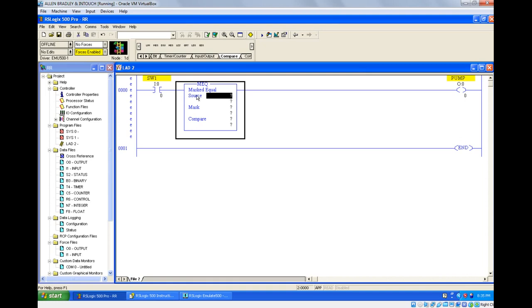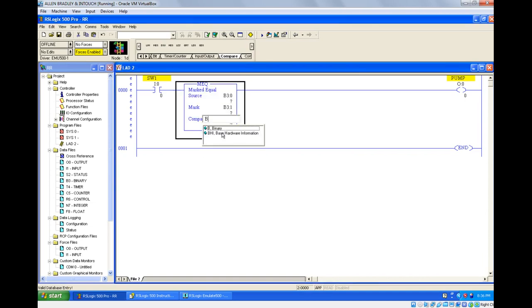Source is the value you want to compare — that value you put here. The comparator value is the reference value, so whatever reference you want to give, you put in the compare parameter. This source is going to compare with the value in the compare parameter. For the address, I am giving B3:0, taking the complete 16 bits. I am also using B3:1 and B3:2.